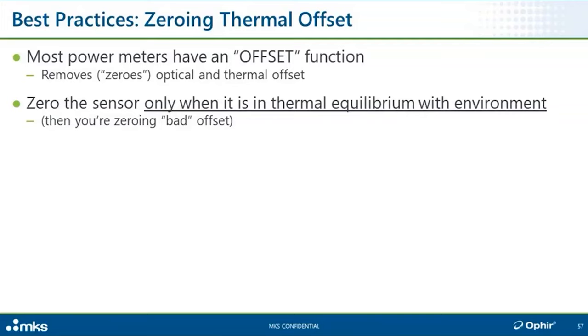this person brought the sensor in from the hot car into his air-conditioned lab, started taking measurements, and was getting a really nasty offset. He didn't know where it was coming from. Turns out that the sensor was hot. It was actually a lot hotter than the air temperature in his comfortable air-conditioned lab. So what happens when a hot sensor is in a cool room? It starts getting rid of its heat as it tries to reach thermal equilibrium. In other words, there's heat moving from the inside of the sensor to outside the sensor body and going off into the surrounding cool air.